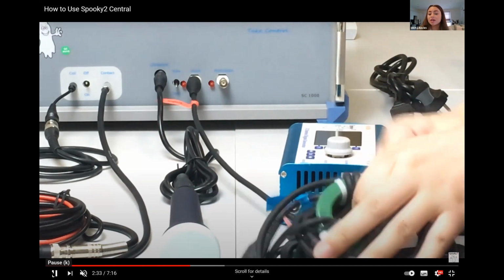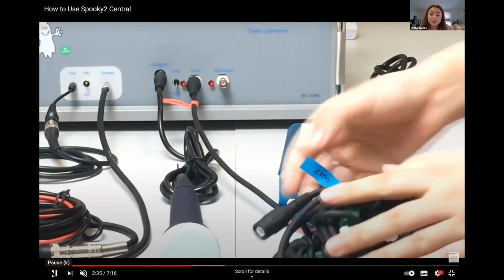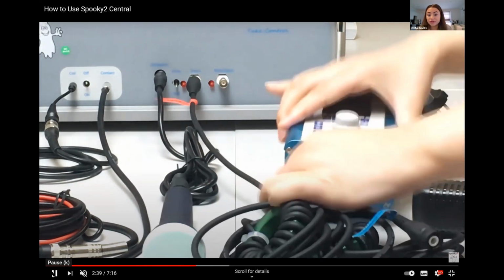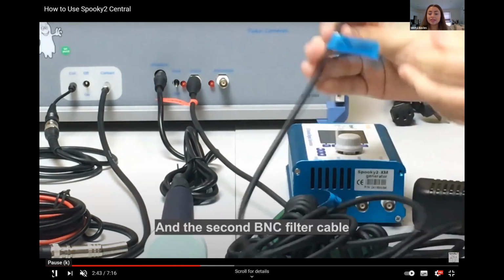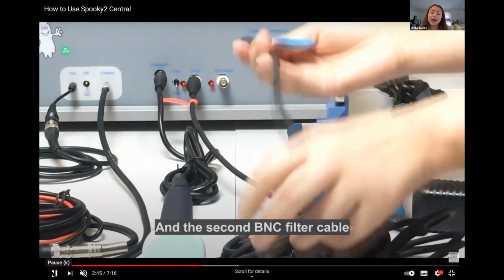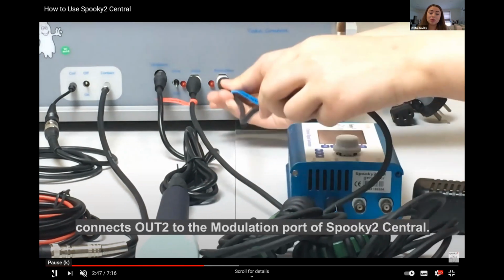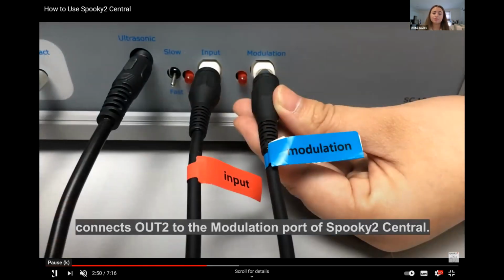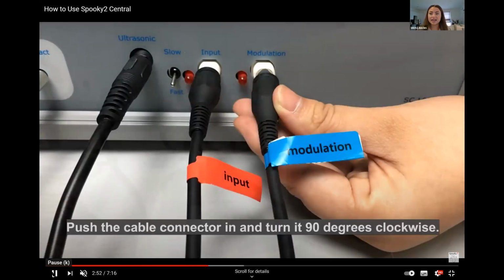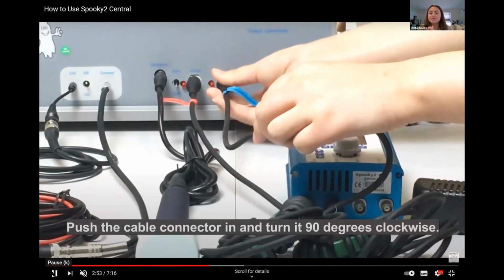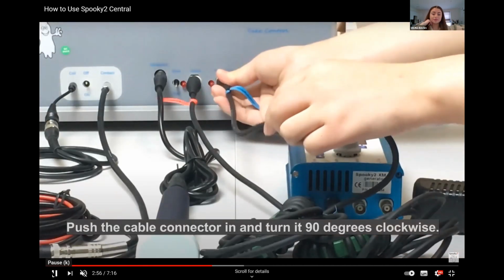Taking the other BNC filter cable, we're now taking Out 2, plugging it into Out 2 of the XM generator, making sure that's secure, and then taking the other end and putting it into the modulation ports as labeled. Then you just rotate it so it's secure.